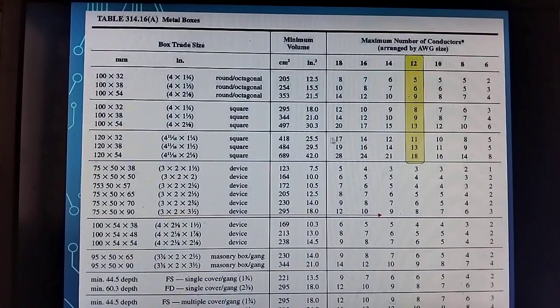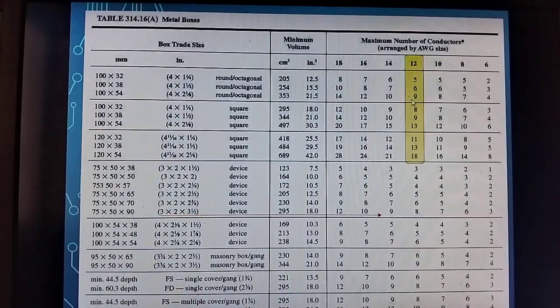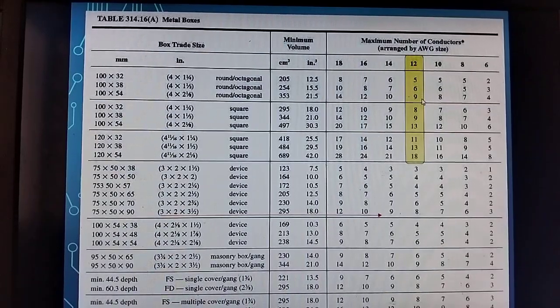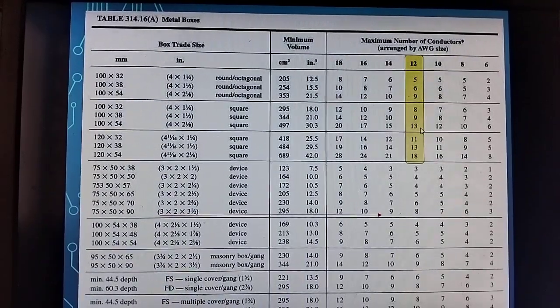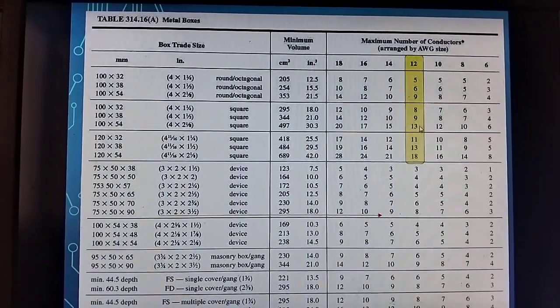So the volume is 30.3, because if you use only octagonal, it only has 21.5, and the allowable capacity is only 9, whereas your wires installed in the junction box are 12. So you must not use the octagonal box, you must use a square box that has a capacity of 13 individual conductors.